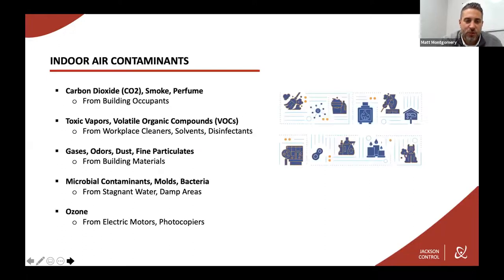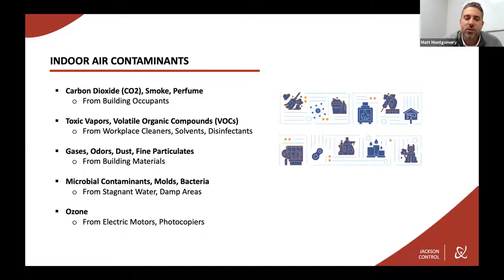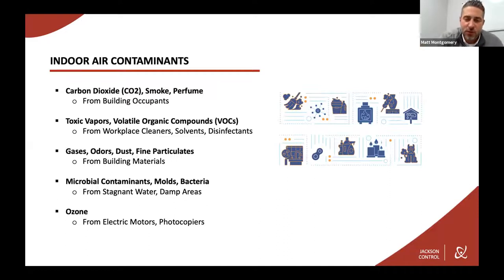Let's look at some of the more common indoor air contaminants. The first is carbon dioxide, or CO2. CO2 is a byproduct of combustion as well as a result of the metabolic process of living organisms. Indoor concentrations without ventilation can quickly reach 1,000 parts per million, compared to outdoor concentrations of about 350 to 450 parts per million.